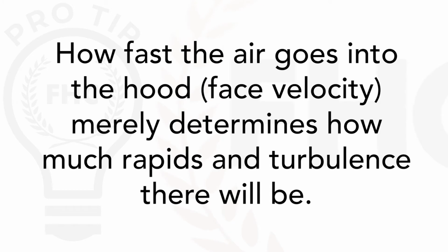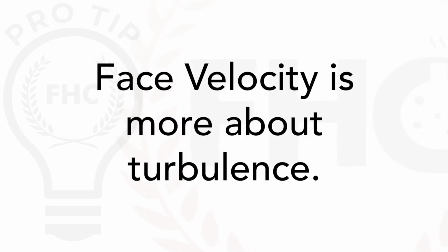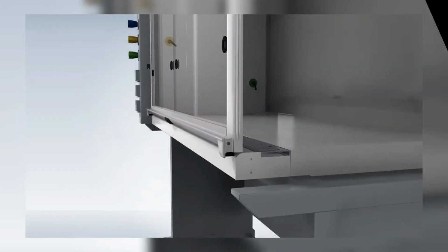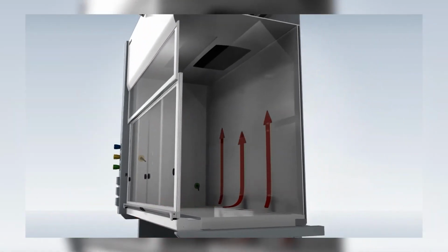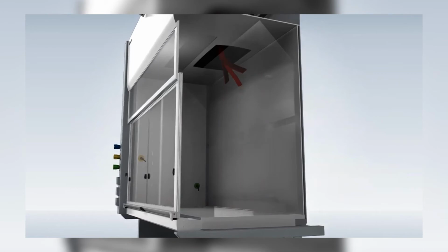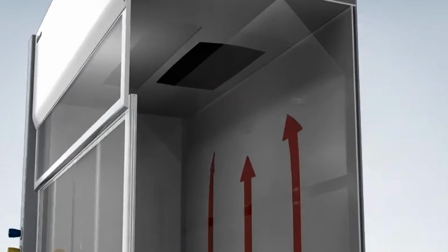While face velocity is a component of containment, it's only one component. How fast the air is going into the hood, which is the face velocity, merely determines how big the rapids and turbulence will be. Raw face velocity is more about turbulence. The direction of the airflow is determined by differential pressure. The stronger the negative pressure at the back of the fume chamber, the more aggressively the air moves into the low pressure parts of the hood, which is mainly the plenum.